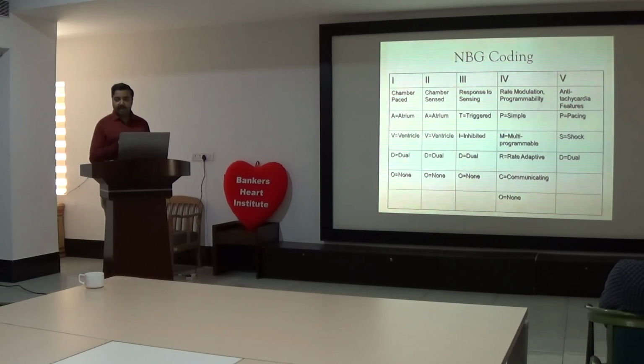Generally, this mode is not used. Only the inhibited or dual mode is used, like VVI: ventricle paced, ventricle sensed; if ventricle activity is there, it is inhibited. In DDD, both chambers are paced, both chambers can be sensed, and it is dual mode. If the atrium is sensed, the atrial pole will not fire, it will go into sensing mode. If the ventricle is sensed, the ventricular lead will not fire, it will go into sensing mode.